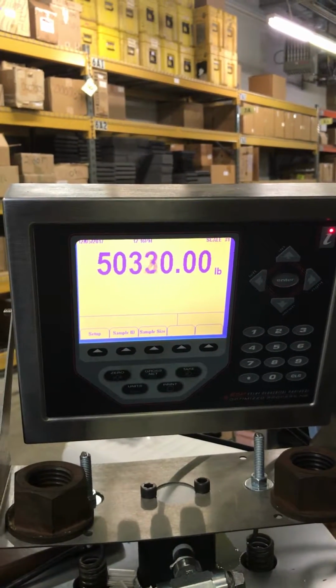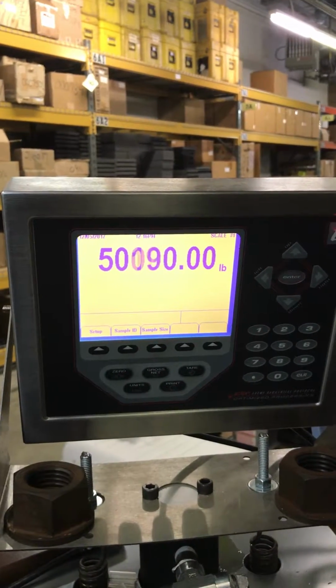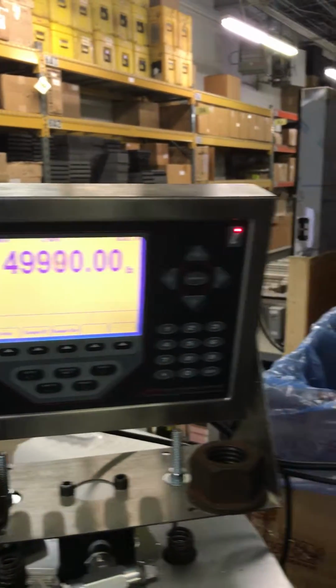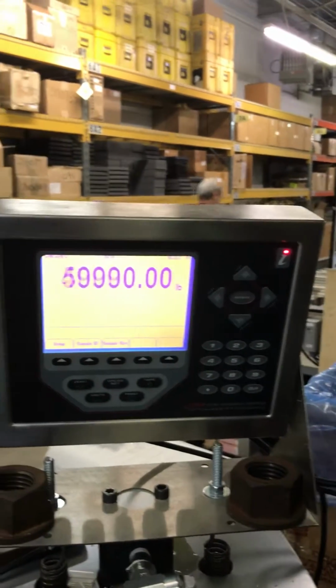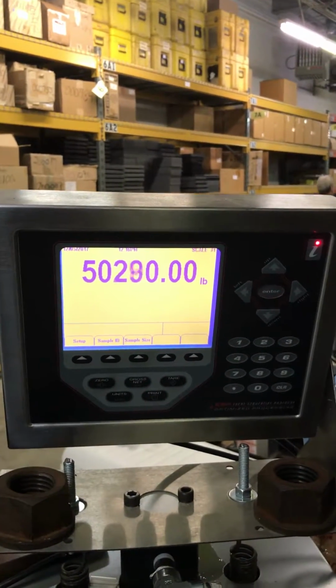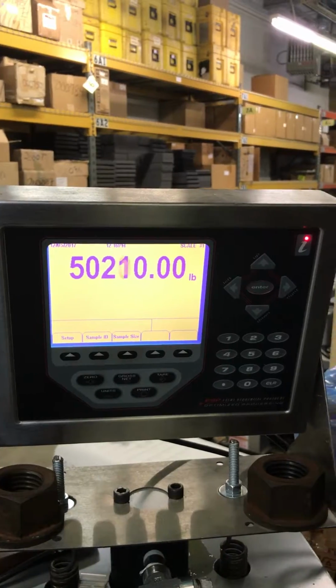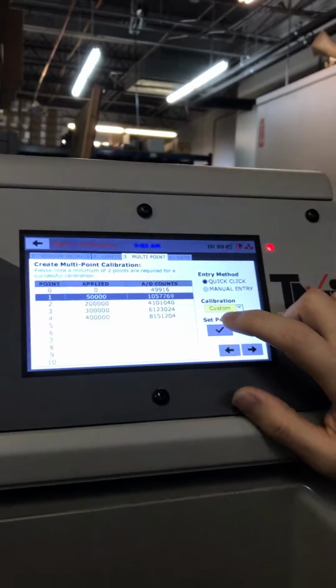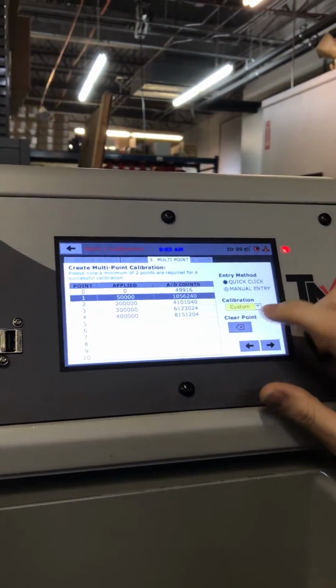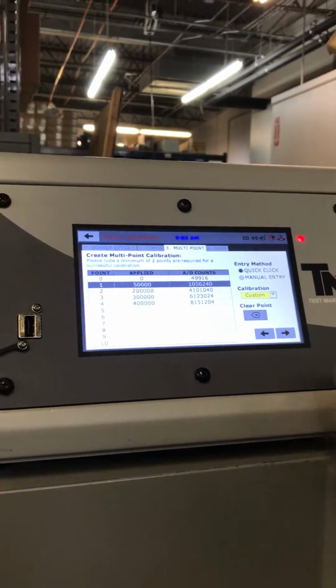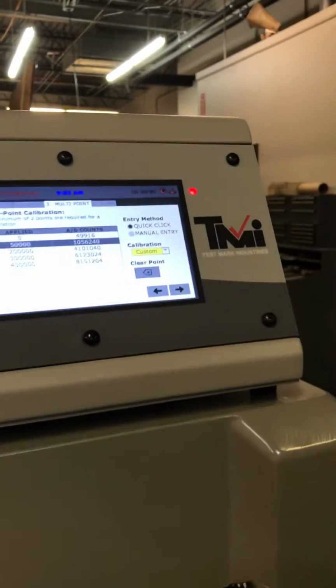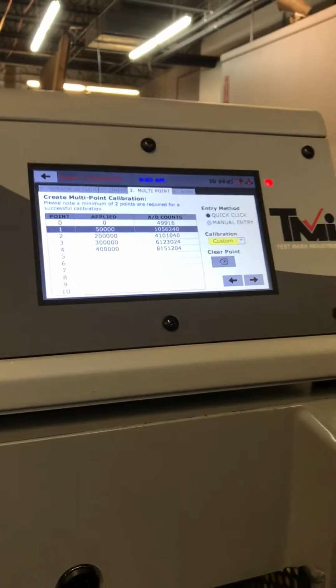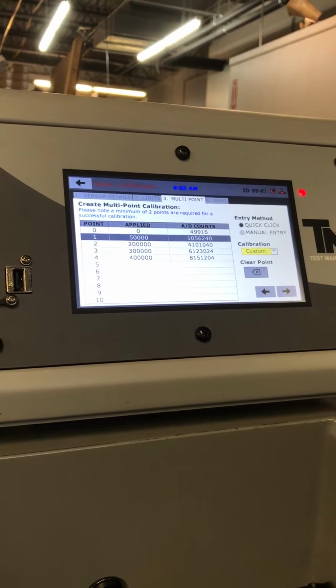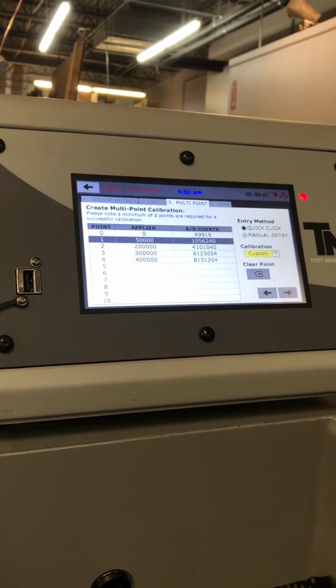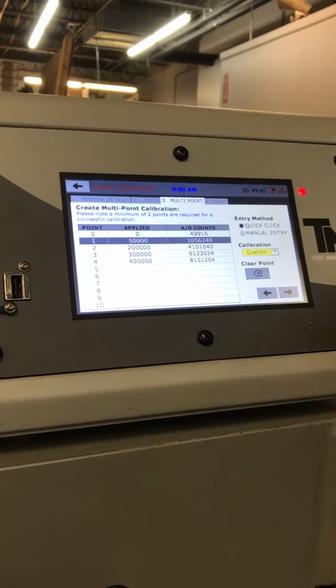So we'll try to get it close to 50,000, and it'll bleed back a little bit, so it's difficult to get exactly right, but your calibrator will have his own technique about how he would like to do it, but we'll get it as close as we can, watching it bleed back and hit set point. So there's a little bit of timing involved. Different people who calibrate have different techniques for the way they like to do it, but for just a quick sample calibration purpose, then this works pretty well.